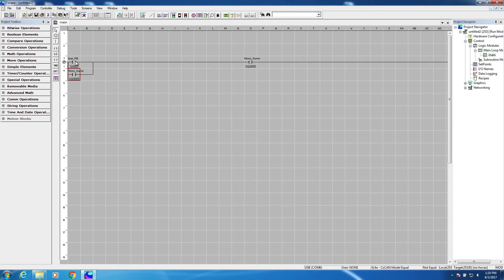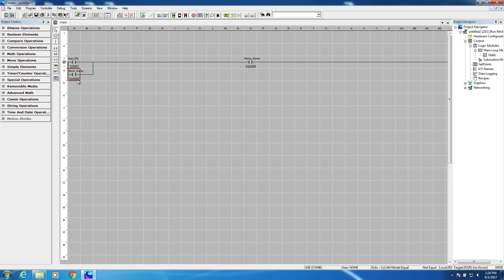Okay, now when I press my start push button and the motor starter starts, the motor starter parallel contact will kick in, keeping power flow around the start push button, so that can be released.